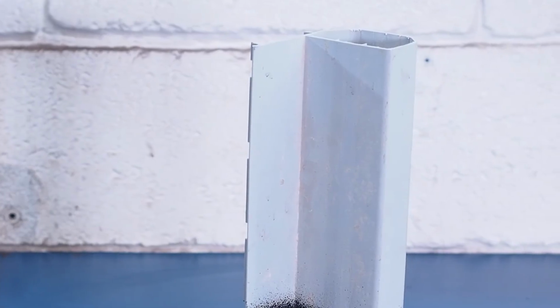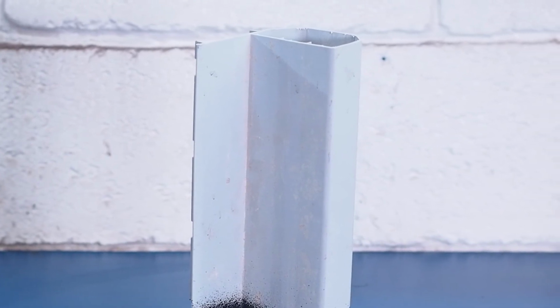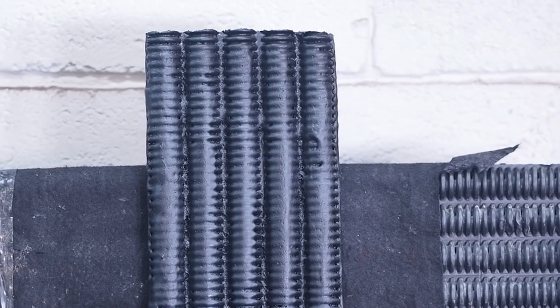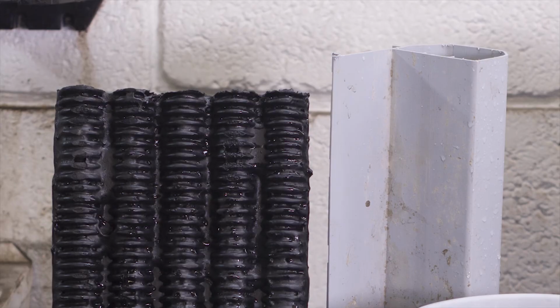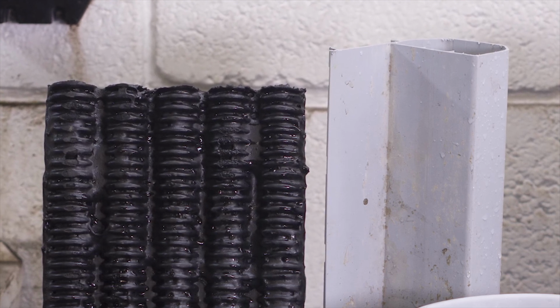To sum up, it appears 2 of the 4 drainage conduits have significantly lower flow rates because of their smaller size and level installation, which again yields a flow rate of 0. As a result, we believe those 2 products do not meet code and should not be allowed.